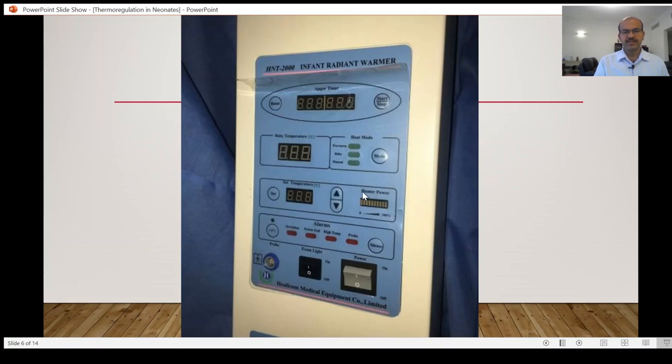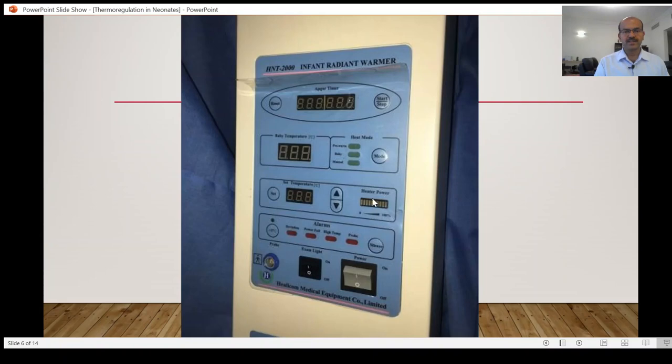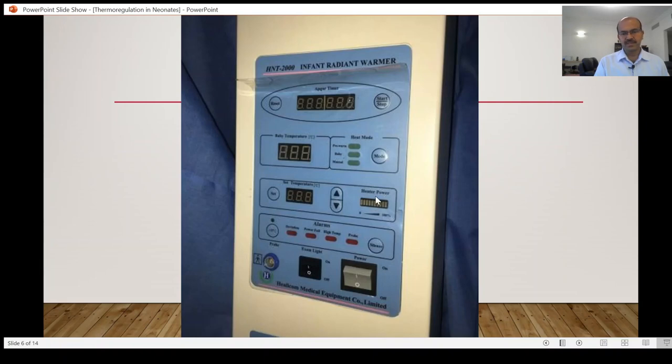So if you look at the design of a panel in most of the radiant warmer systems, you have this area where you have the extent to which the heater output is used. We have from 10 marks most of them, so from 10 percent to 100 percent heater output. If there are no lights on here, it means there is no heater output. If you have five marks, it means 50 percent of the heater output is on.